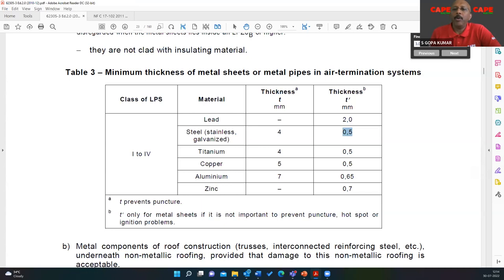Now, aluminium sheet on main head house, 0.7 mm thick. So 0.7 mm aluminium, 0.65. If it is more than 0.65, of course 0.7 means lightning may puncture the aluminium sheet. You have to decide whether you can live with this puncture, or you can also live with the hot spots and arcings due to this puncture. If you cannot live with that, you have to put an air termination at the top of the roof. Preferably, you install an air termination mesh and connect it to the sheet itself. That is the best method.